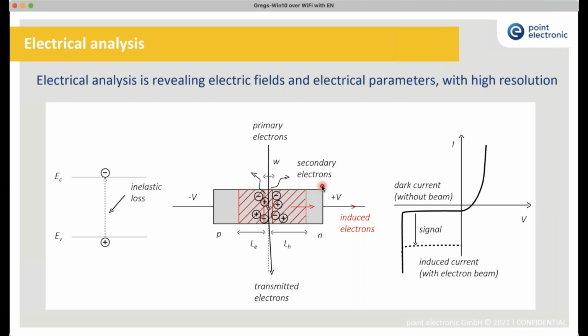As the primary electrons interact with the sample, they excite electrons with sufficient energy that some of them will leave the sample. And when the secondary electrons leave the sample, we need to put those electrons back. And they will be drawn from our circuitry back into the sample. A term that has more recently been used to describe this is secondary electron beam induced current, which is quite a long acronym. Other things happen at the same time. So the transmitted electrons go through the field, and they are slightly deviated. So you could pick that up as well with differential phase contrast, for example.